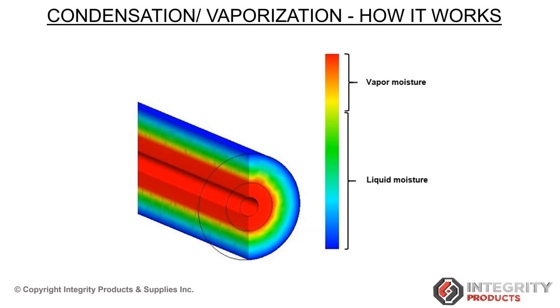Yeah, because you're now giving the moisture room to move to the 6 o'clock position on the pipe and then freely leave. Absolutely. Whether it's vapor or liquid moisture, you've created that 6 millimeter standoff between the insulation and the exterior cladding, which allows that moisture then to leave the system. Exactly. In a perfectly designed insulated system, condensation is likely expected at the jacketing location. And the presence of the perforated dimple wrap stops the moisture from going back into the system again.